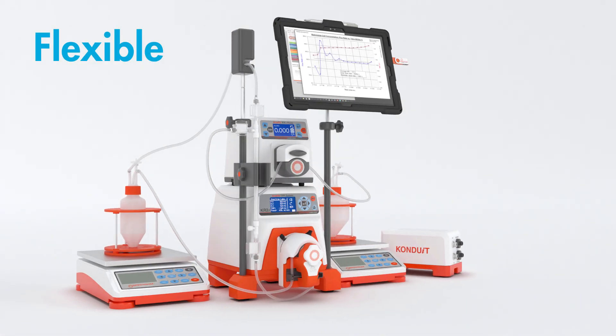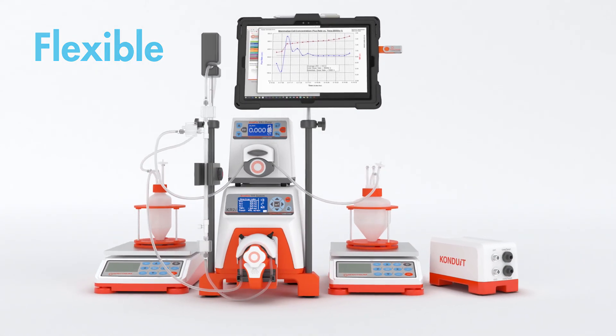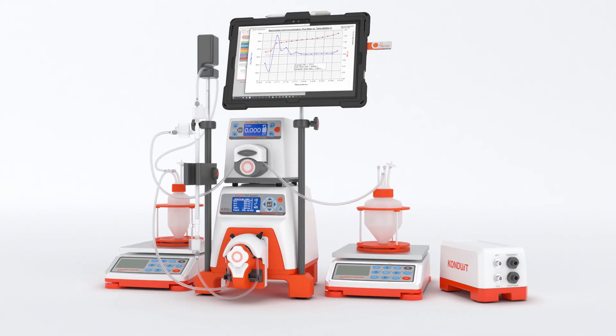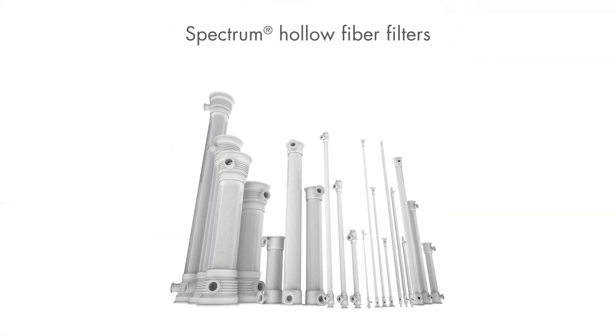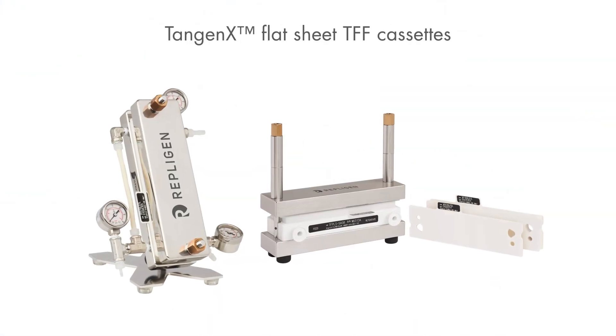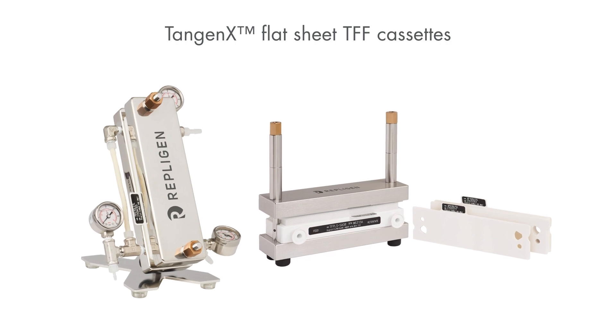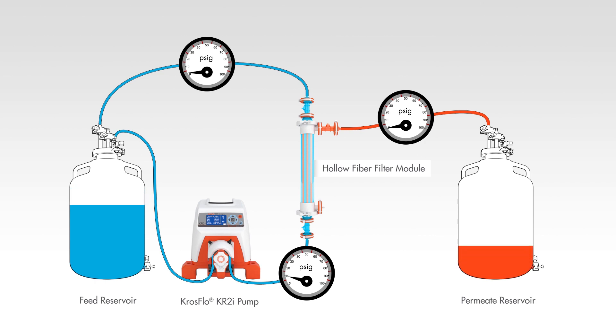The KR2i TFF system is designed for running volumes anywhere from 10 liters down to a few mils. There's no other system on the market that can have that level of versatility. It's flexible to run either hollow fiber or cassettes, anywhere as small as 20 square centimeters of membrane area to as large as 0.35 meters squared.